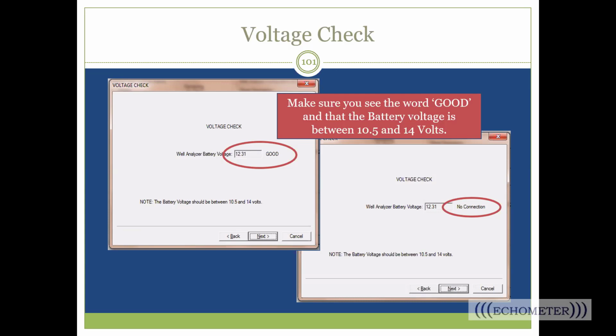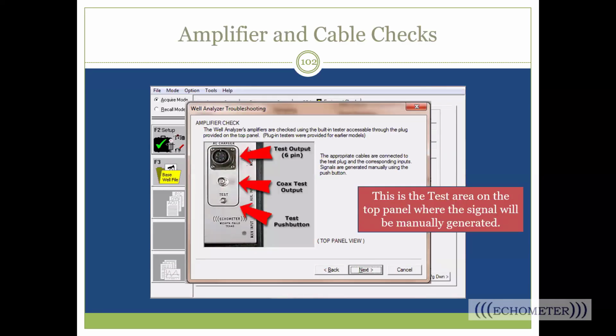If it's 10.5 or lower, you've got enough power to have everything turned on and communicate, but you don't have enough power to send that 12 volts through your cable to the solenoid. So you want to make sure that you've got good battery power. Now, the next thing it's going to do is check your cables.